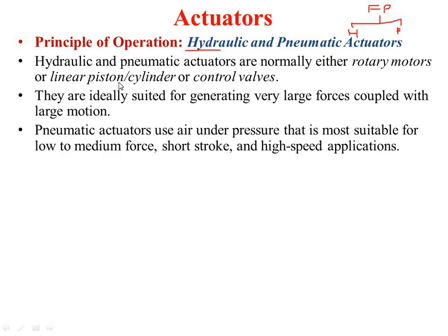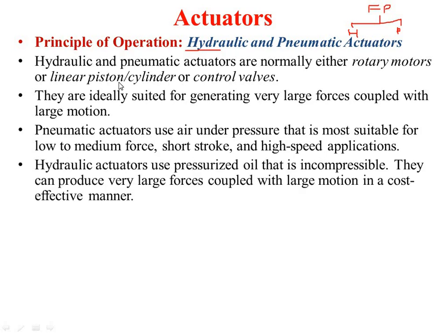The pneumatic actuators generally use air under pressure, which is most suitable for low to medium force, short stroke and high speed applications. So whenever you require a medium force with short stroke and high speed, generally pneumatic actuators are preferred. Hydraulic actuators use pressurized oil, which is incompressible and can produce very large forces.